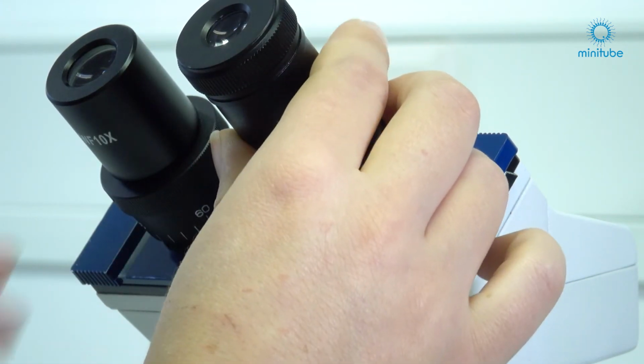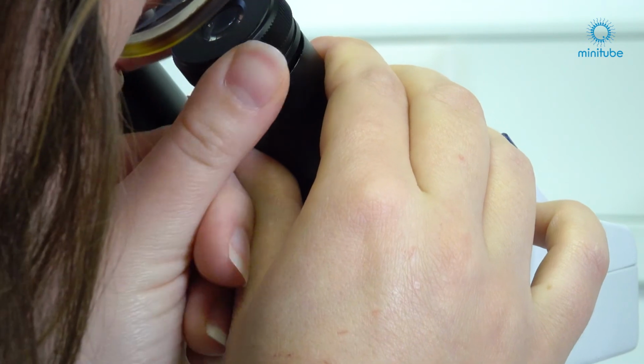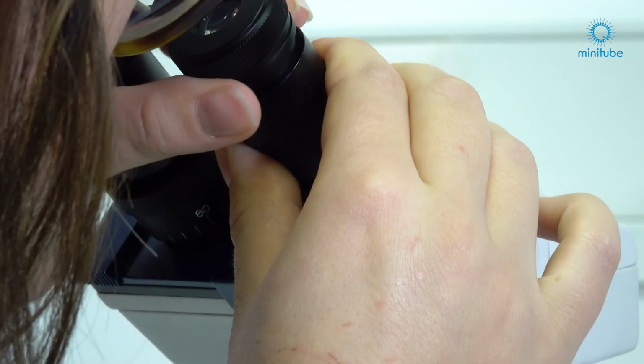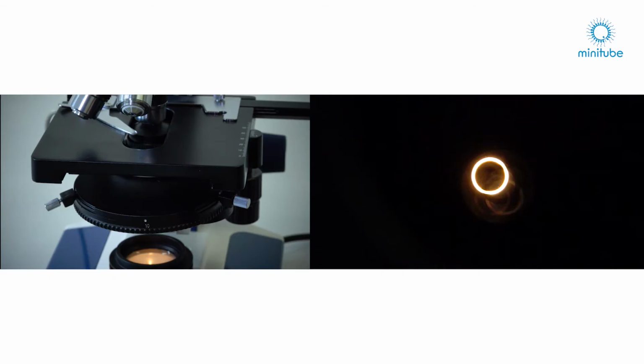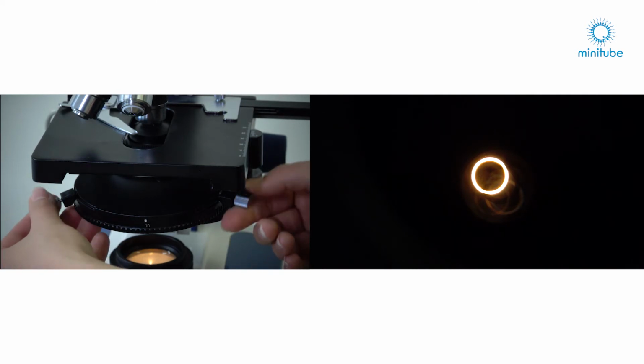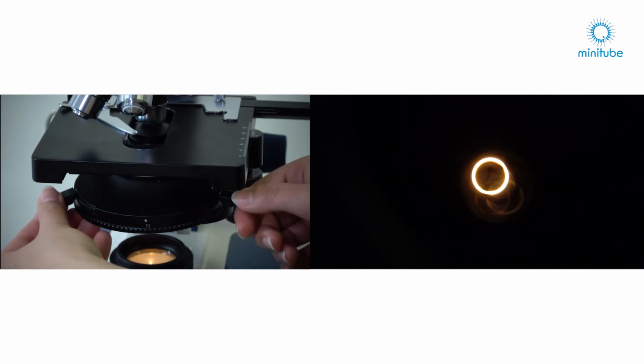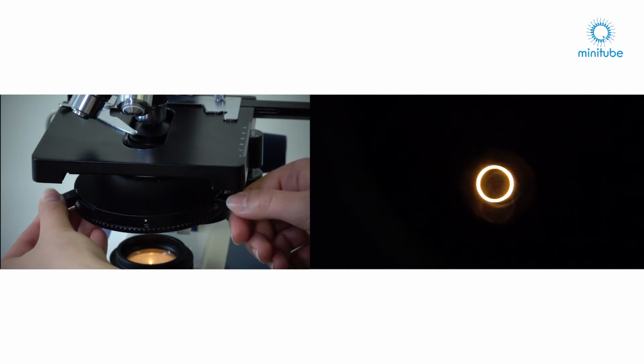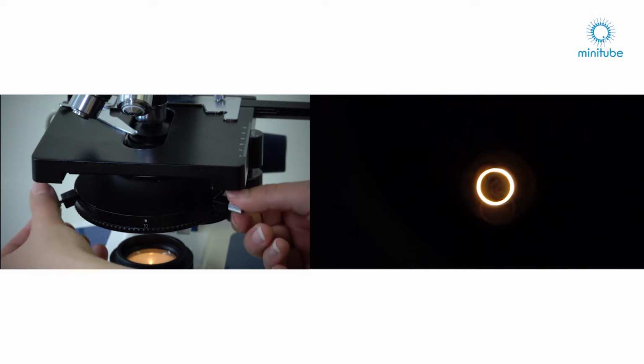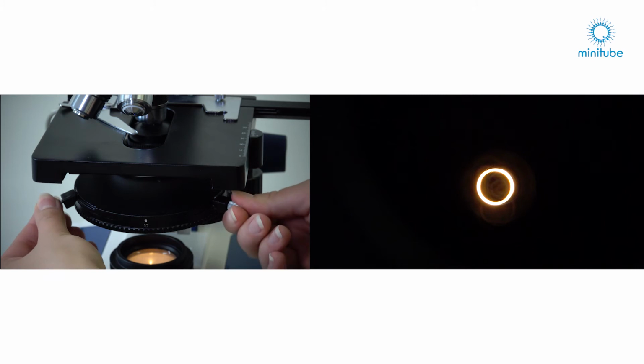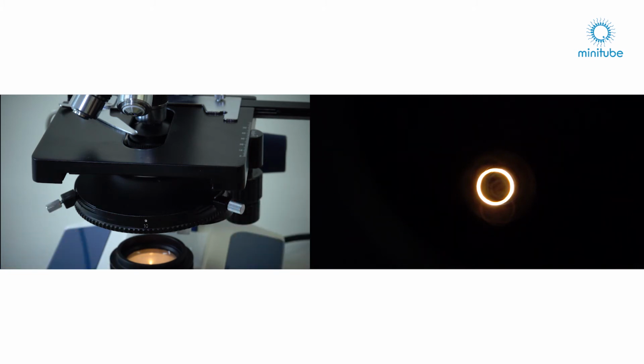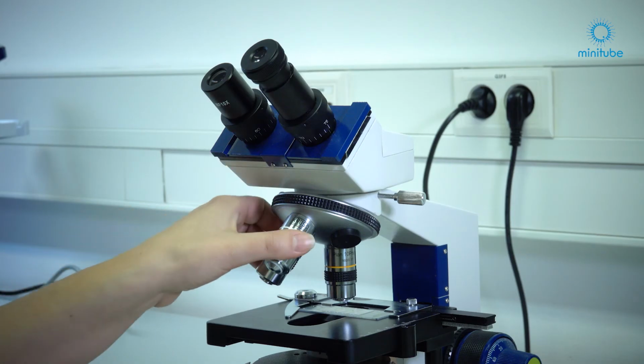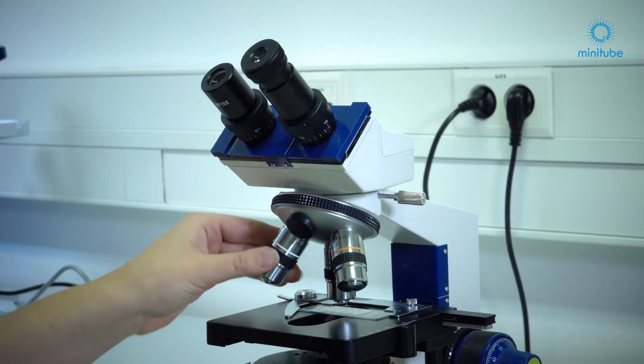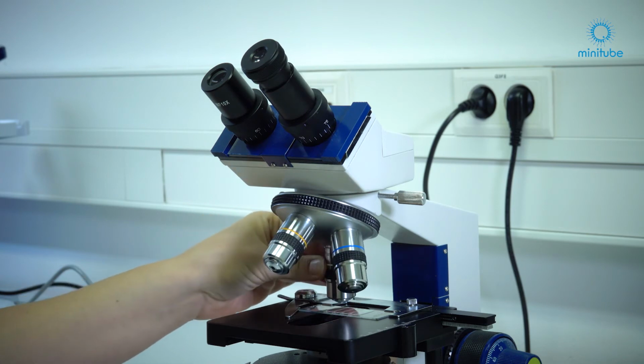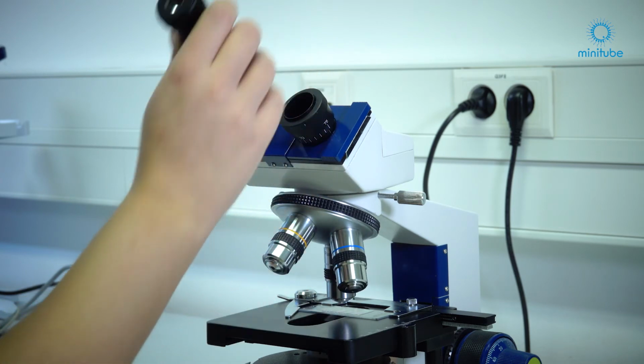Focus the phase rings by adjusting the eyepiece of the centering telescope accordingly. Use both centering knobs, which are located on the front of the condenser. Now you have to achieve a full overlap between the lighter annular diaphragm in the condenser and the darker phase ring of the objective. When done with this objective, repeat this procedure with every other phase contrast objective and then replace the auxiliary microscope with the regular eyepiece.